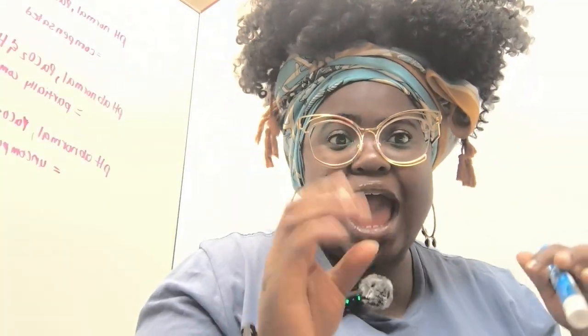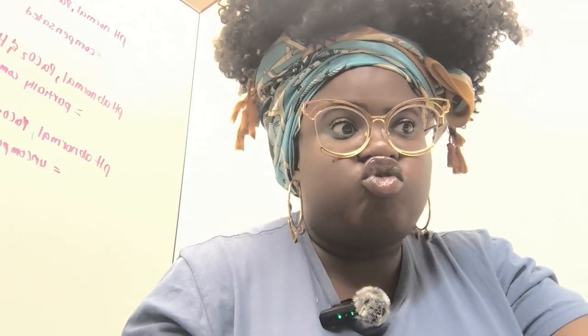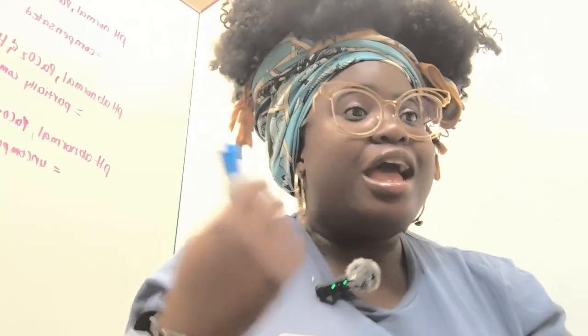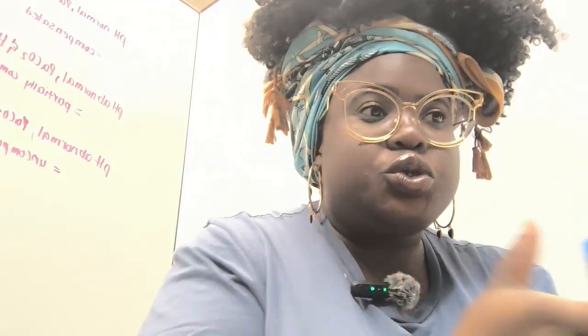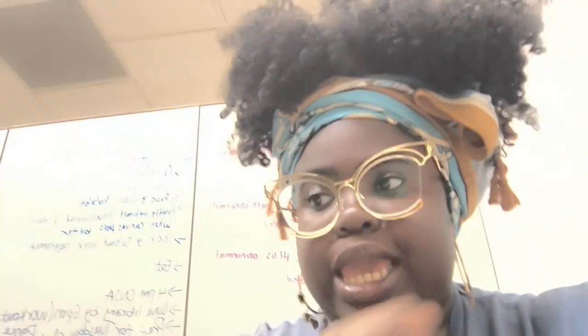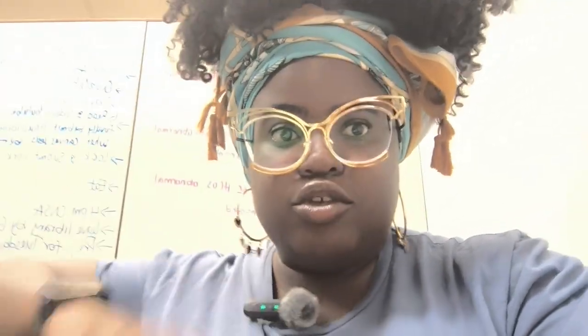So when Mr. R's high pressure alarm kept going off, the alarm was treated instead of finding the cause of why it was sounding in the first place. The cause: he had a mucus plug blocking his tube. His body was trying to push air past the blockage, and the ventilator was saying, I'm using too much pressure to deliver this breath. You should have suctioned. Instead, the pressure limit was changed and it was made worse.